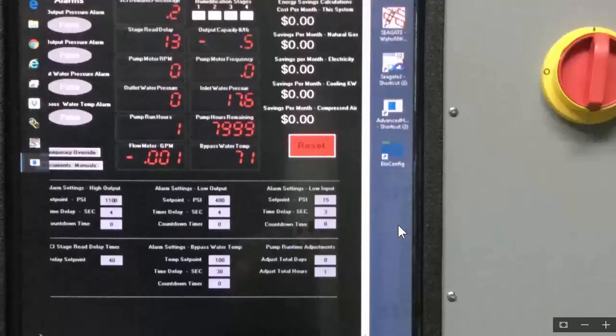Now you can see that this system is not actually running. In fact, it's a new system. It really doesn't have any run hours on it at all, and that's indicated right here. Pump run hours 1, pump hours remaining before inspection of the pump 7,999 hours. So this pump has just run a little bit, and you can see that this is the output, or this is the JCI demand. It's at 0.2. It goes from 0 to 100%.